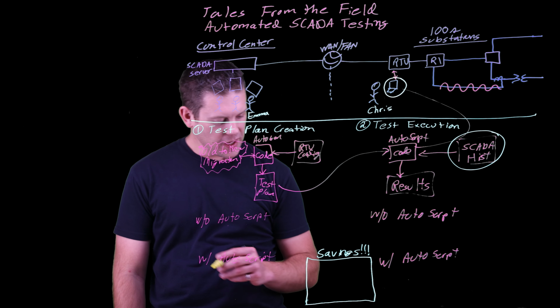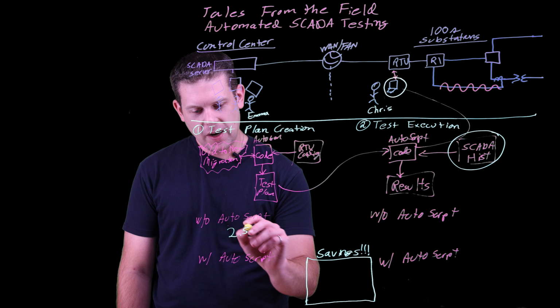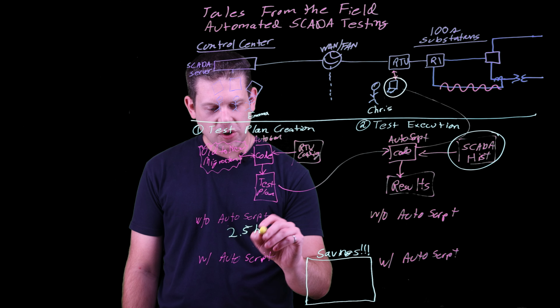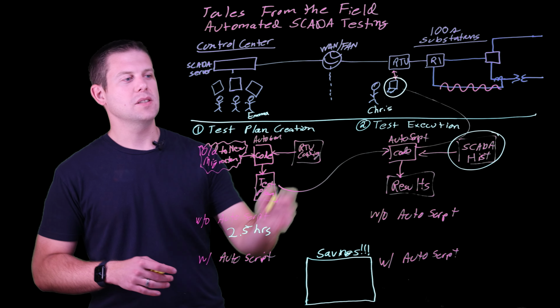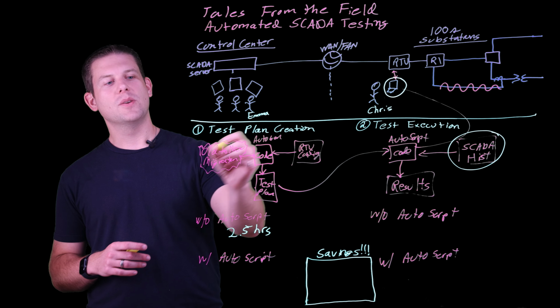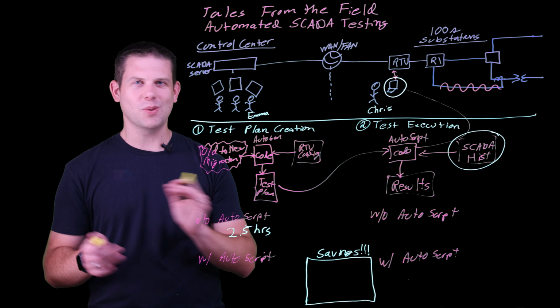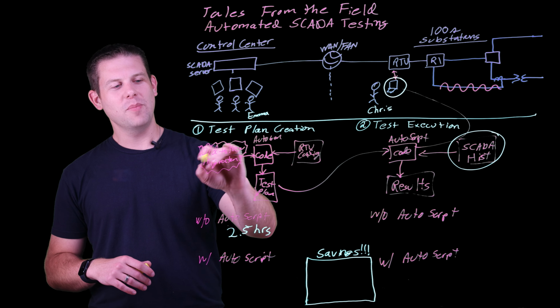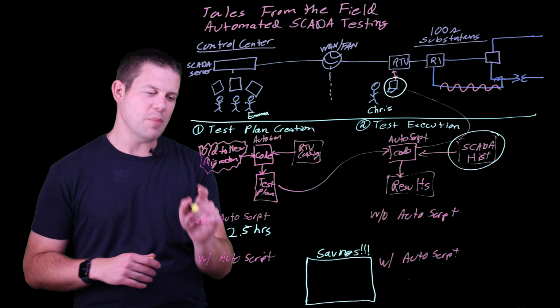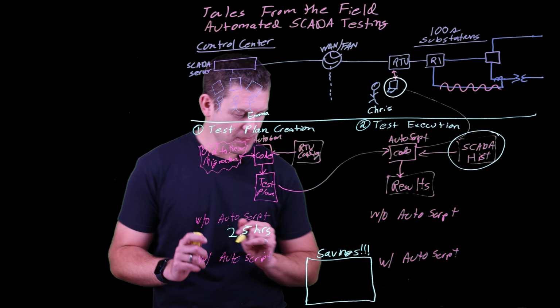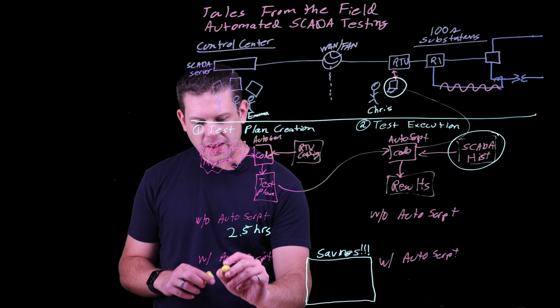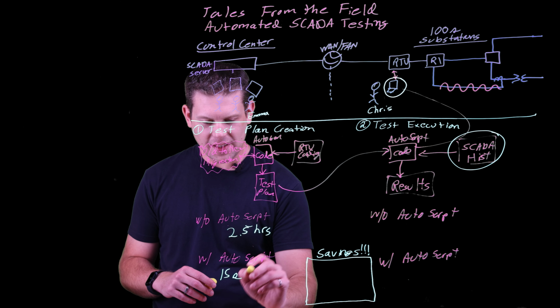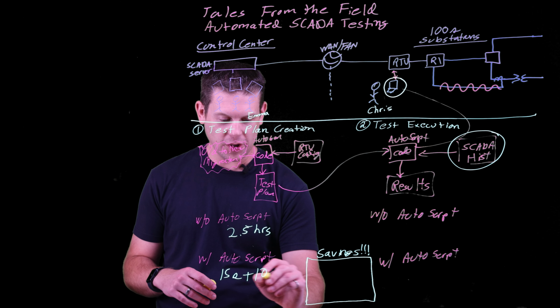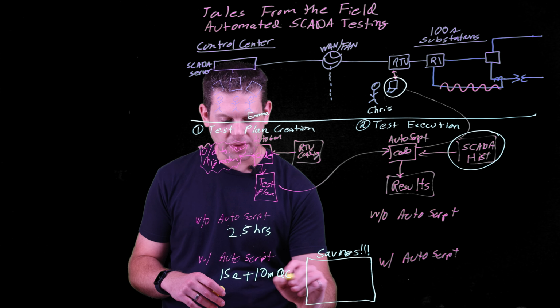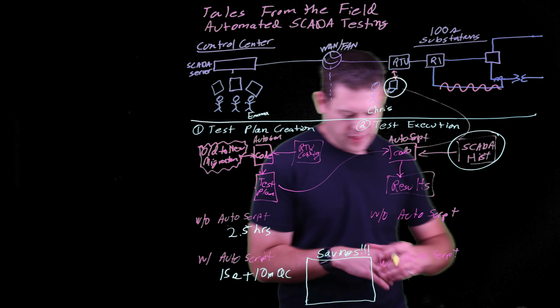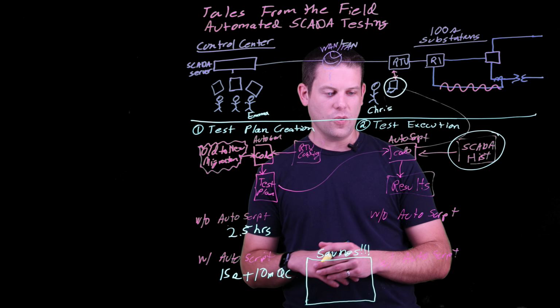Looking at test plan creation alone, without automation we're looking at about 2.5 hours to do this manually - comparing the RTU config directly point by point, very grueling work, then comparing it to the migration file point by point to see if things line up. Our software was able to create these test plans in 15 seconds, plus 10 minutes of QC for good measure - always need that engineer review and oversight.